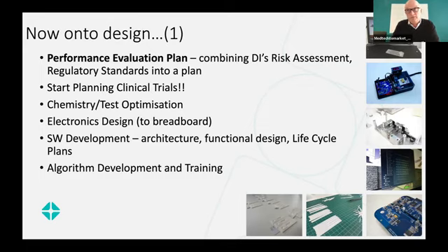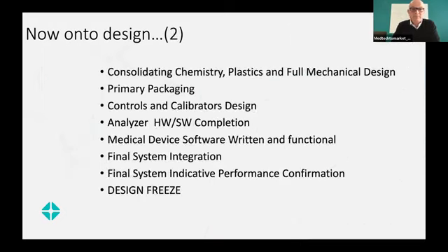Software development, so a lot of diagnostics or medical device systems are software only applications. So at this point, you'll be detailing out the architecture, the functional design, life cycling plans for the relevant regulatory standards for software, and also any algorithm development and training. So a lot of this work will have already been picked up from your research project and your discovery project, but now it needs to start to be consolidated. You're now thinking of developing this into a product and firming everything up.